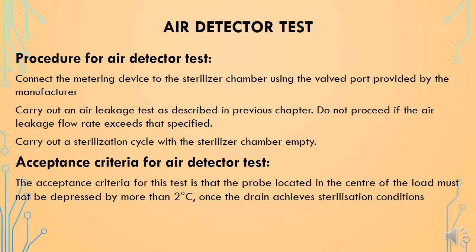The acceptance criteria for the air detector test is that the probe located in the center of the load must not be depressed by more than 2 degrees Celsius once the drain achieves sterilization conditions.